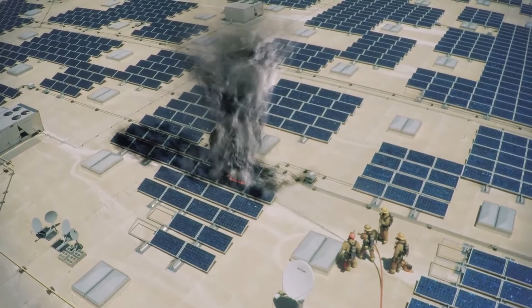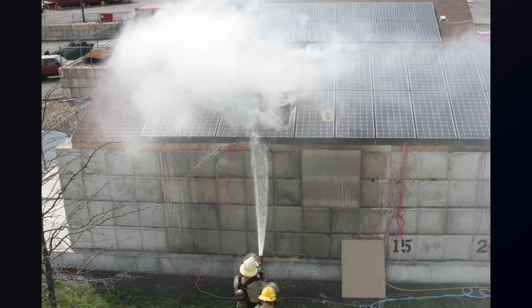Firefighters have had questions about how operationally to fight fires on buildings with energized PV systems. UL in 2010 received a grant from the Assistance to Firefighters Grant Program to study just that. The first test examined the shock hazard due to the presence of water in PV systems during suppression.